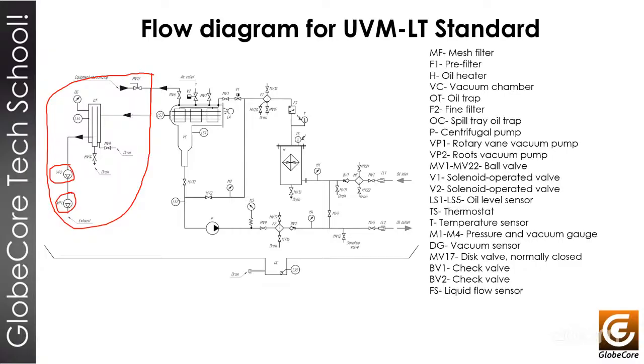Here we have the oil trap, and the sensor that will detect if we have oil in this trap. That really helps if, for some reason, the machine has a problem and the oil comes from the vacuum chamber to the oil section: the machine will stop because it detects oil in this line. Another thing we have in this machine is the valve out of the vacuum chamber.